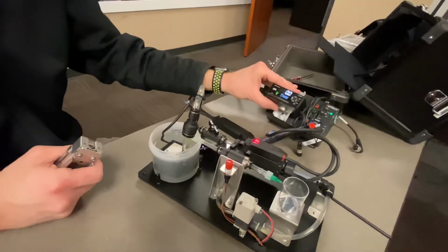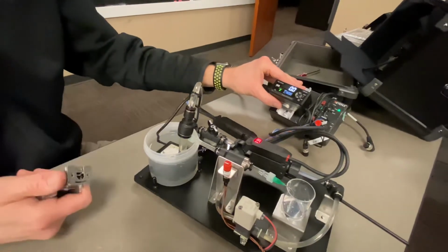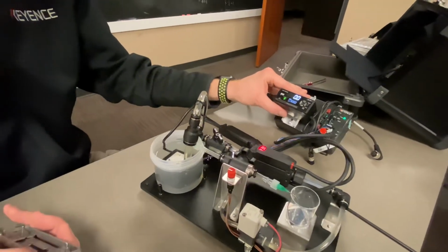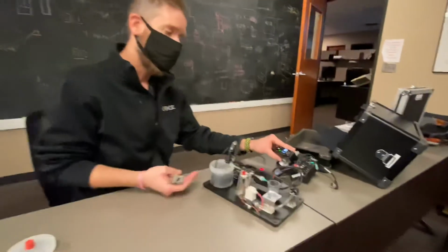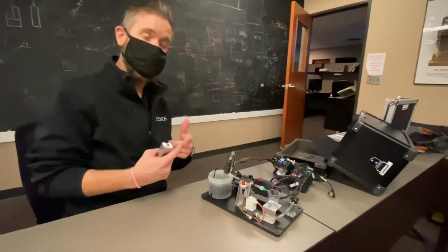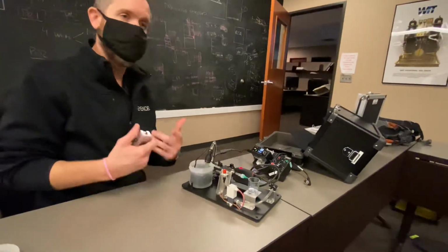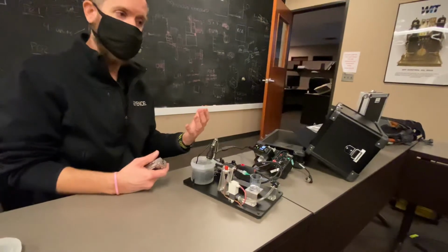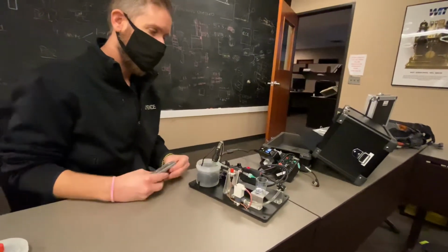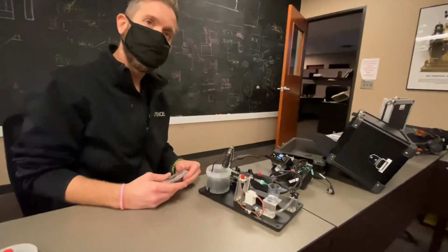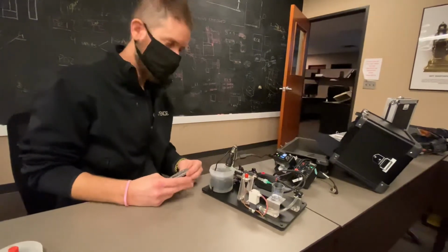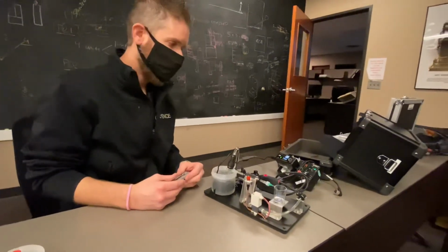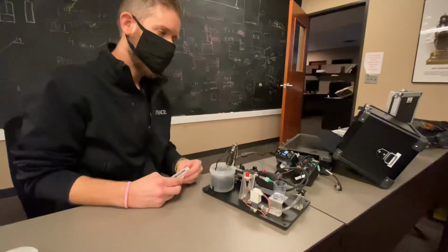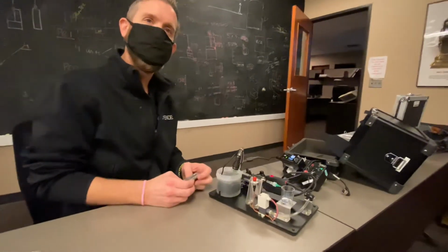Yep, to the controller. That controller is going to provide a couple of different ways you can pull that output. I believe the intention is to use a pulse output from the flow sensor, so we can certainly set that up. You can draw the output via 4 to 20 milliamp, and we can configure the pulses for whatever pulse rate we want, representing a certain flow. That'll allow us to make this not drag and drop, just a drop-in replacement of the existing flow meter.